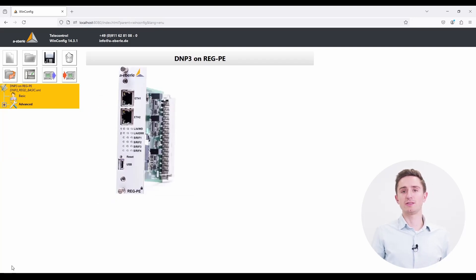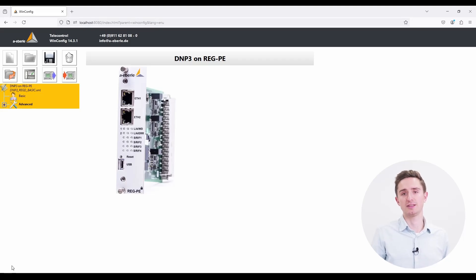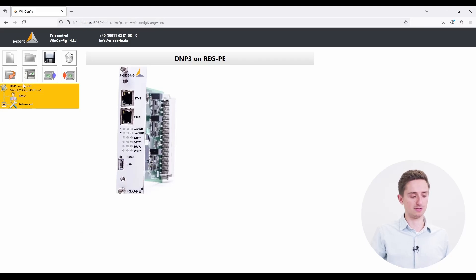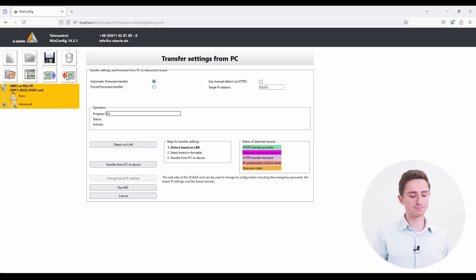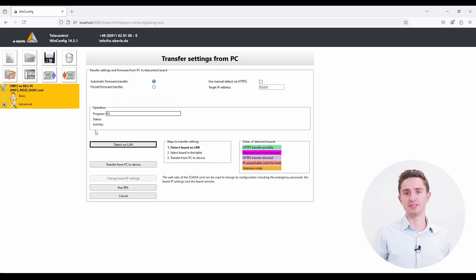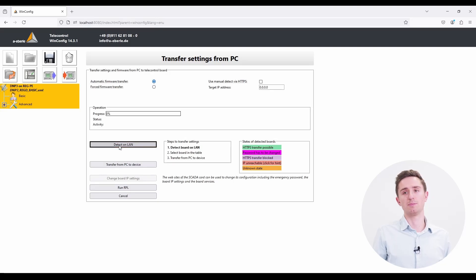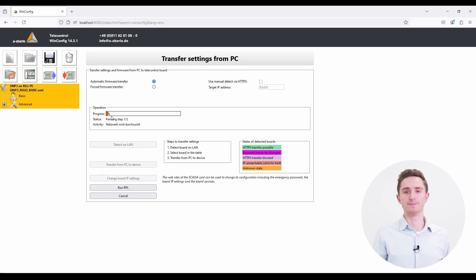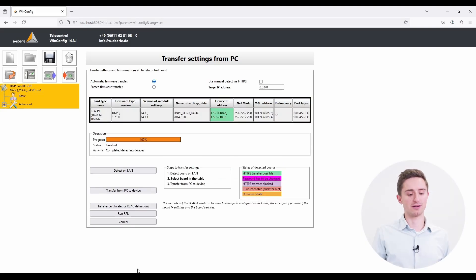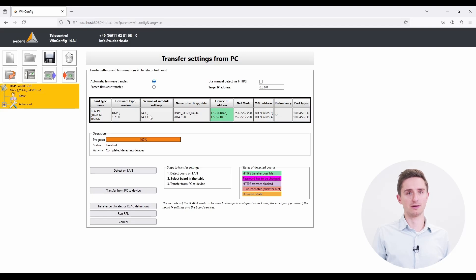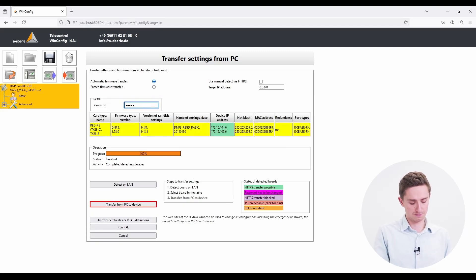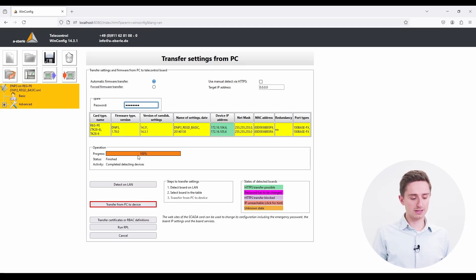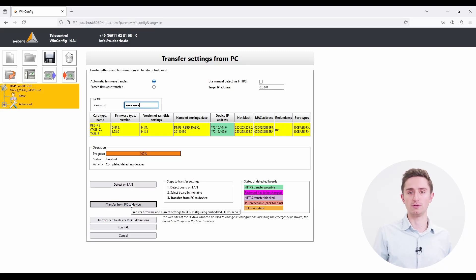After changing the settings in the parameter file, you might want to upload the parameter file again to the SCADA card. Therefore, select your parameter file and press transfer settings to the SCADA board. Do a detect on LAN again and wait until the PC found the card in the network. The PC found the card in the network. We select the card, enter our password again, and transfer from PC to the device.